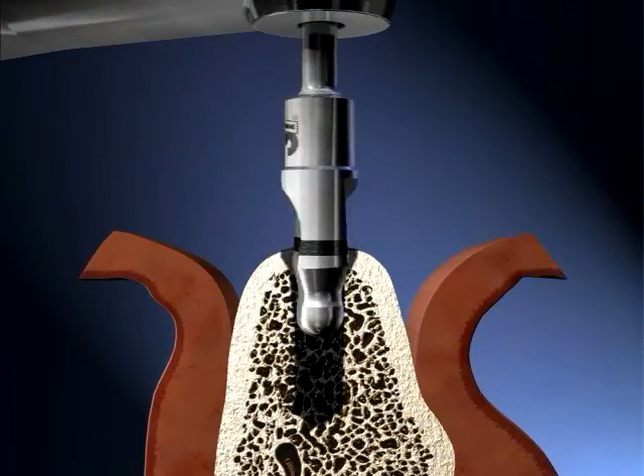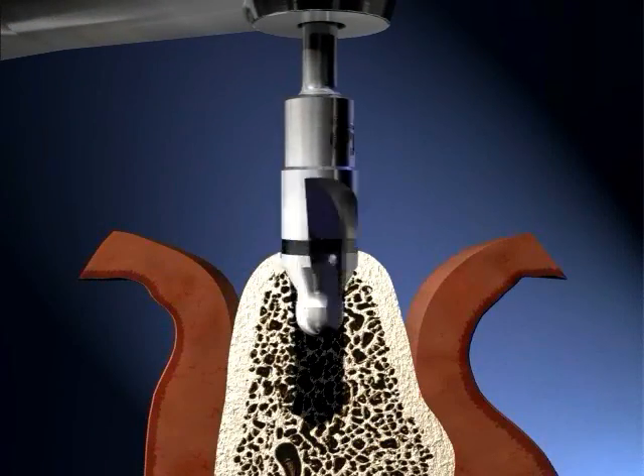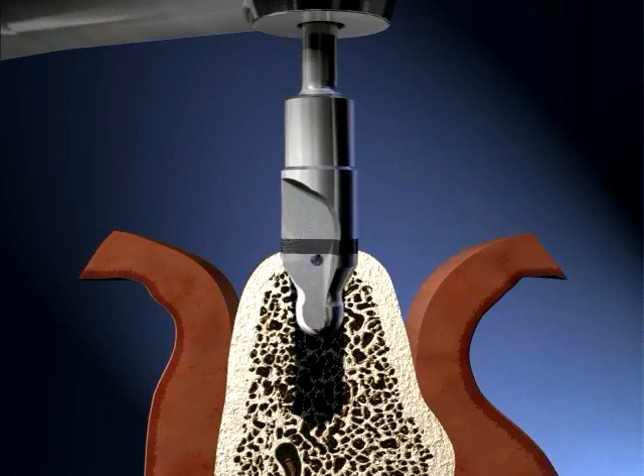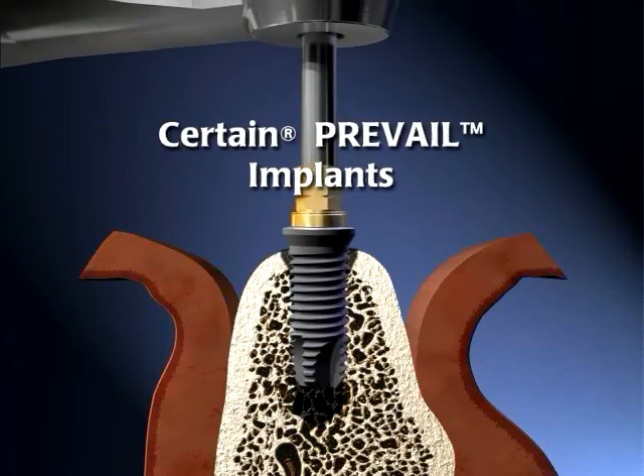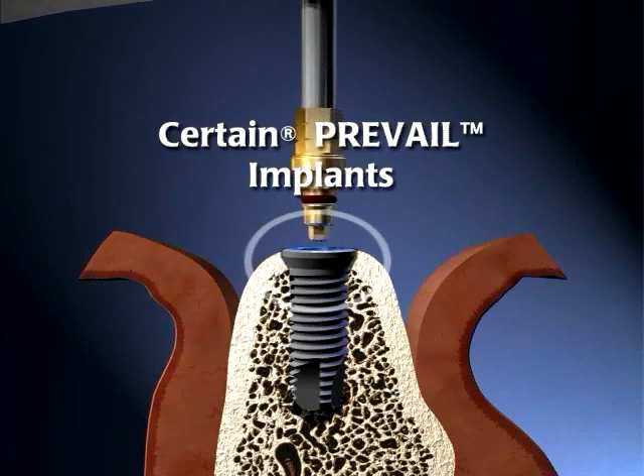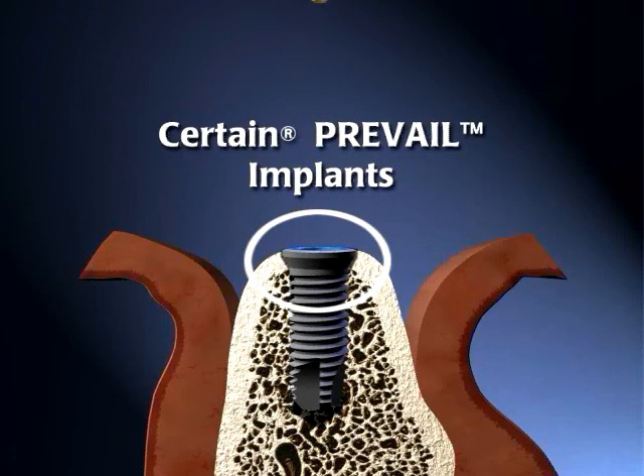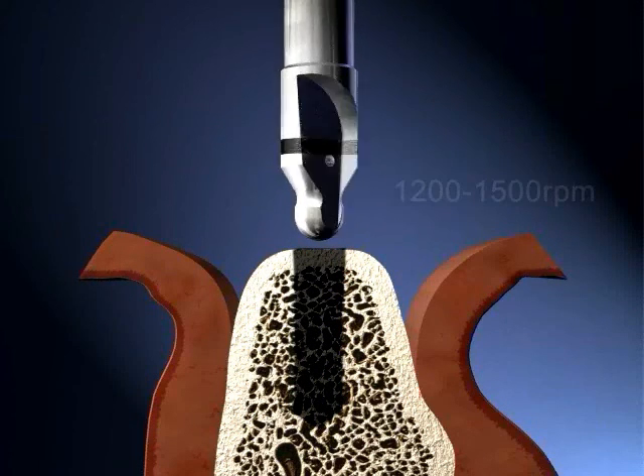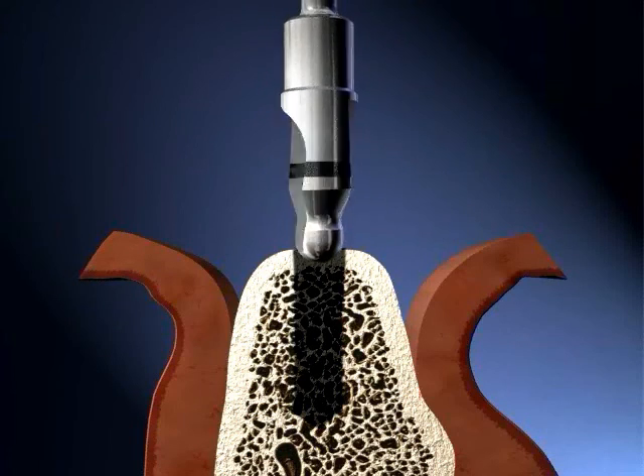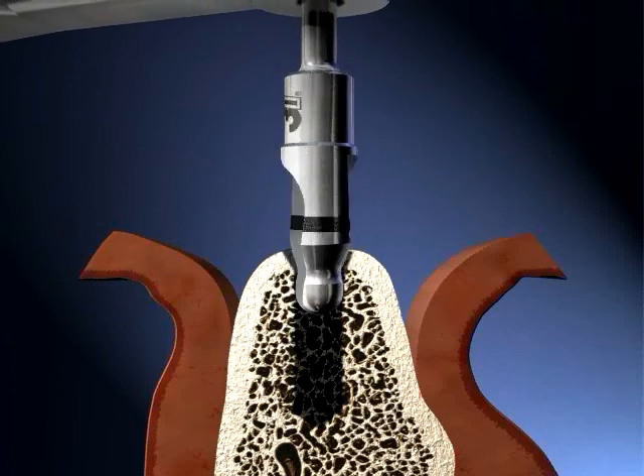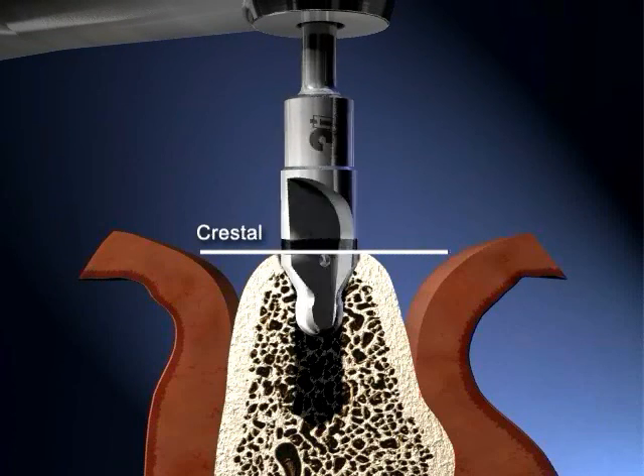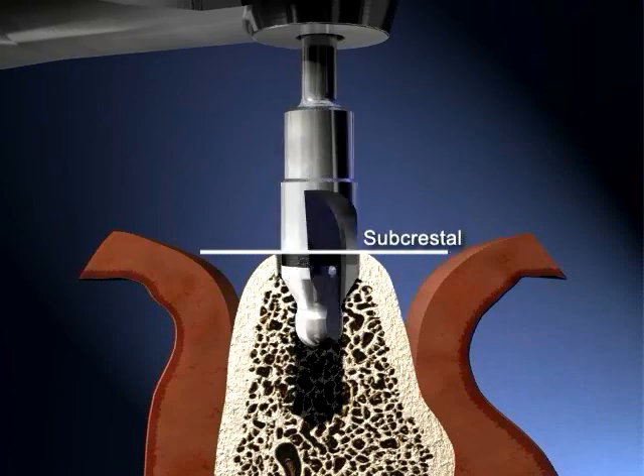The countersink drills are used to prepare the expanded collar portion of the osteotomy for placement of certain PREVAIL implants. The expanded collar portion of the implant creates stability and helps lock the implant at the coronal aspect. Countersink drills should operate between 1200 to 1500 RPM. For crestal placement, drill to the leading edge of the 1 millimeter wide laser line. For subcrestal placement, drill 1 additional millimeter to the top of the line.